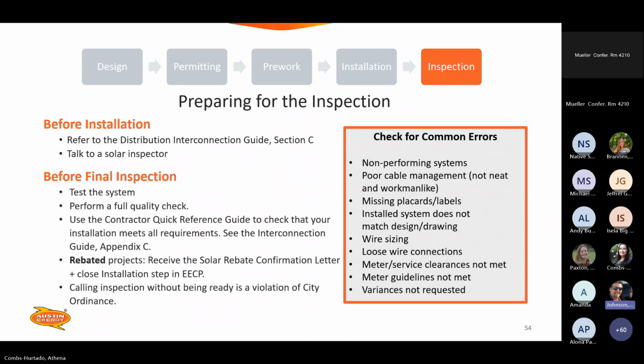And preparing for an inspection, refer to the Distribution Interconnection Guide, Section C. Talk with your solar inspector. And before the final, test your system. Turn it on, commission it, test it, make sure it actually works. When we show up and we test for full functionality, that's part of it. It has to work. The customer is paying for this much. That's what they should get. The one line says that this is what they're getting. That's what the customer is paying for. That's what they should get. And it should all work when we get there.